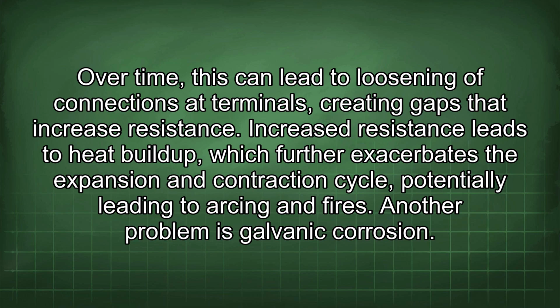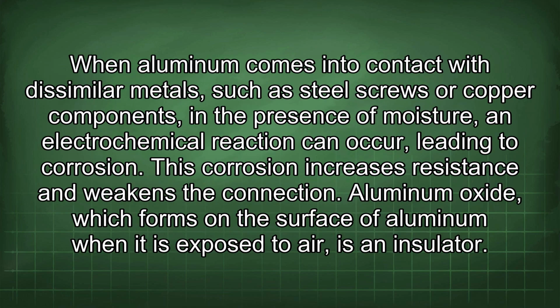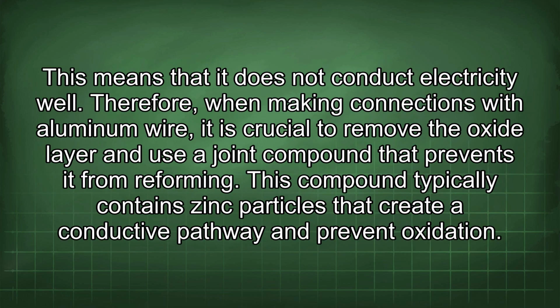Another problem is galvanic corrosion. When aluminum comes into contact with dissimilar metals, such as steel screws or copper components, in the presence of moisture, an electrochemical reaction can occur, leading to corrosion. This corrosion increases resistance and weakens the connection. Aluminum oxide, which forms on the surface of aluminum when it is exposed to air, is an insulator. This means that it does not conduct electricity well.